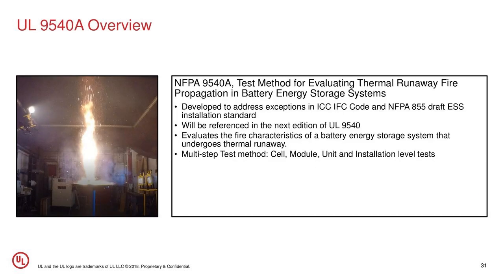Moving on, 9540A was also mentioned in Chuck's presentation. This is the test method we developed to address the exceptions in the fire code and in NFPA 855. It was published almost a year ago, and we're now on the third edition because we've had a lot of learning conducting this testing and have made changes. It's developed to determine whether a system can meet those code exceptions, but even meeting 9540A, it still has to be approved by the AHJ. All those exceptions require large-scale fault and fire testing and AHJ approval, so that's still needed. We'll be referencing it in 9540.